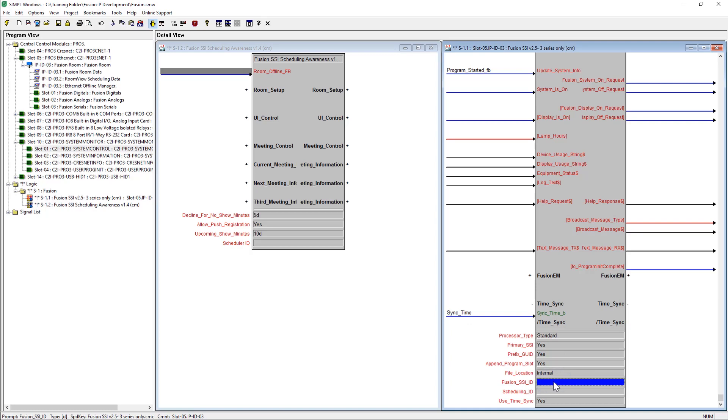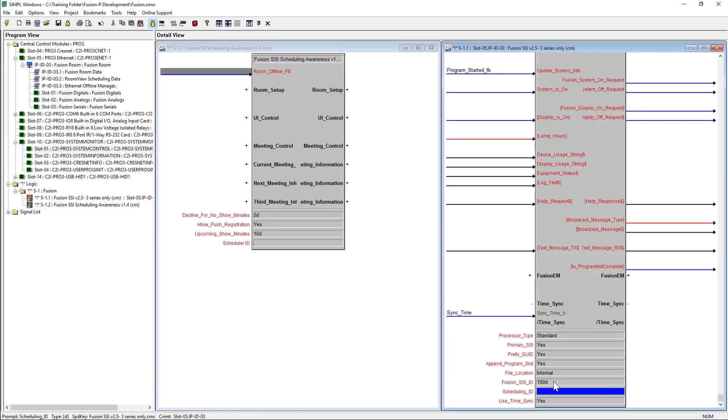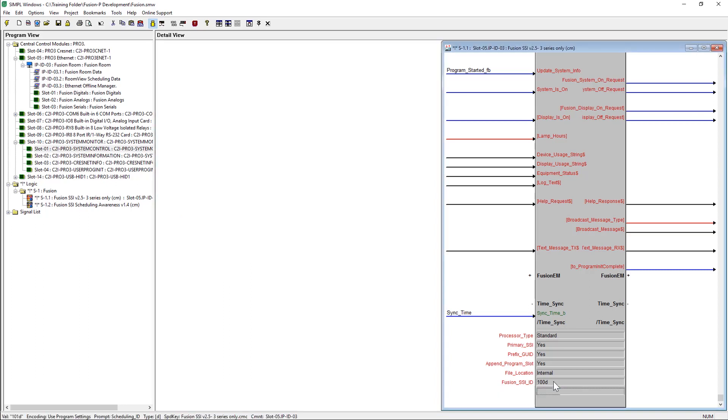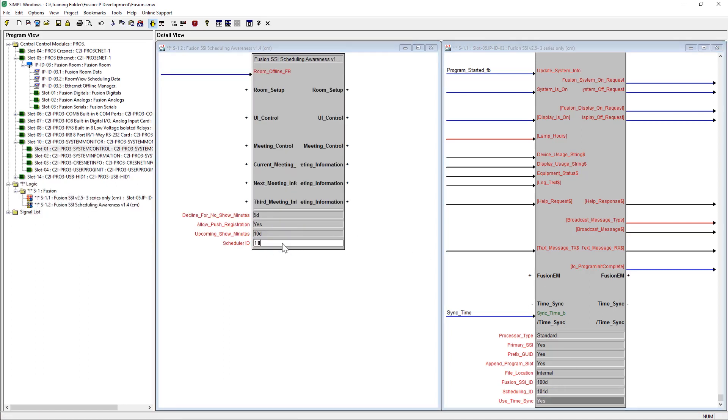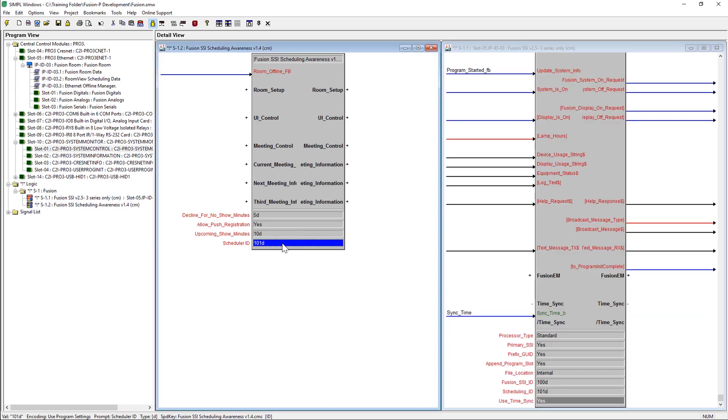The Crestron Fusion SSI ID parameter must be a non-zero number. If multiple Crestron Fusion rooms are in one program slot, this value must be different on the various main SSI modules.